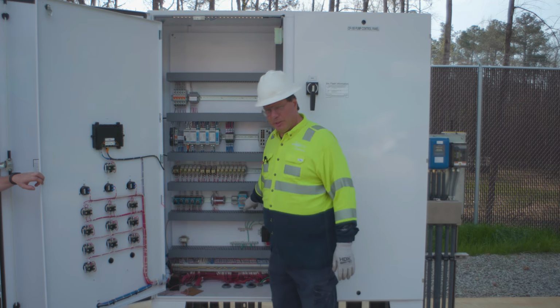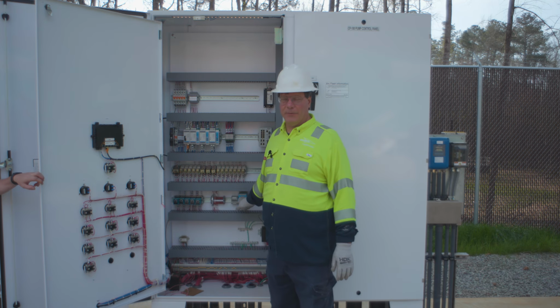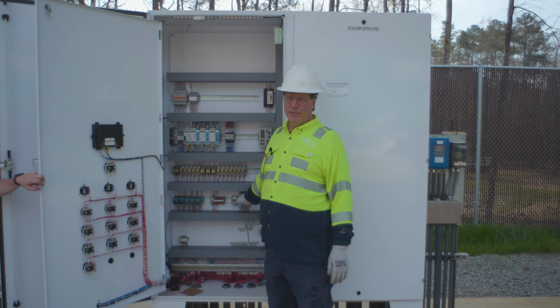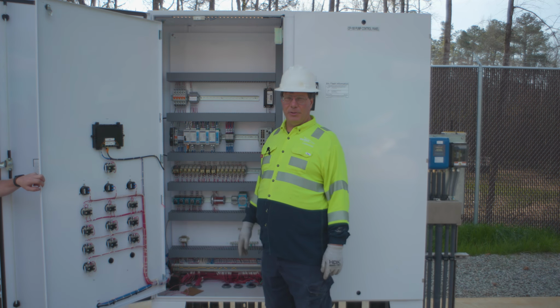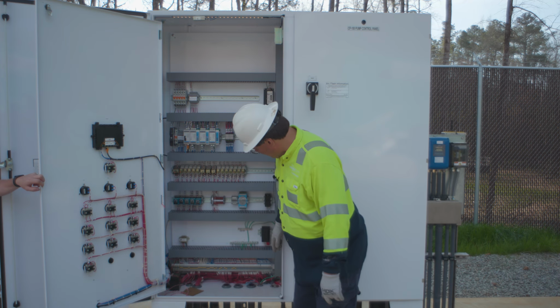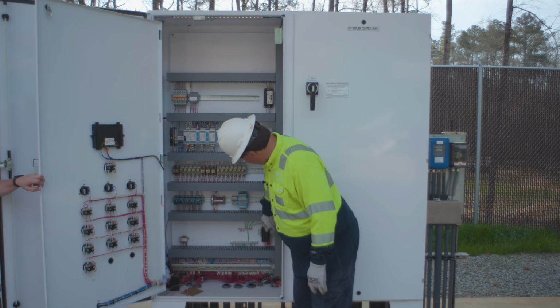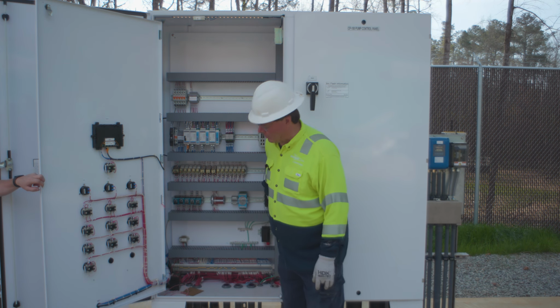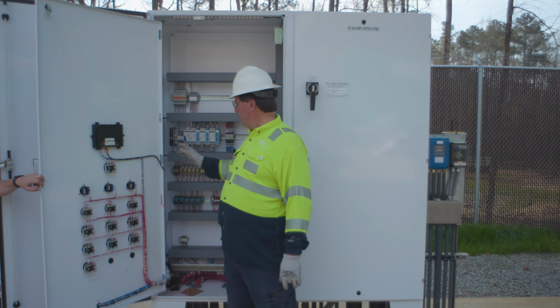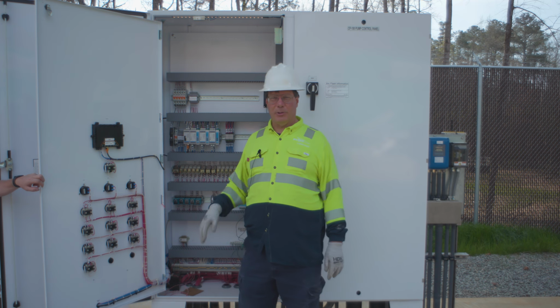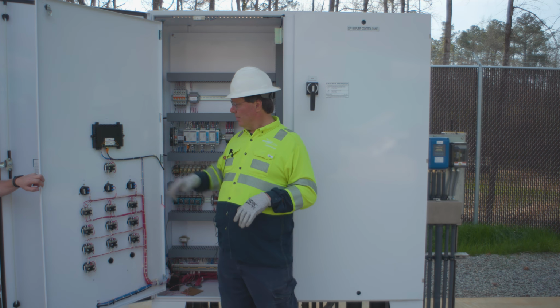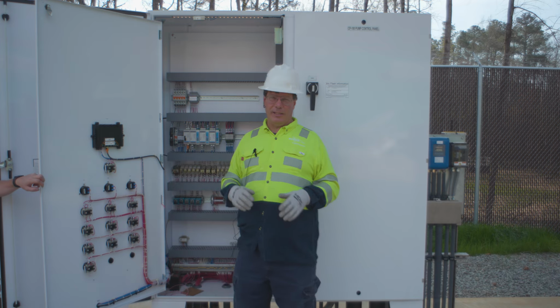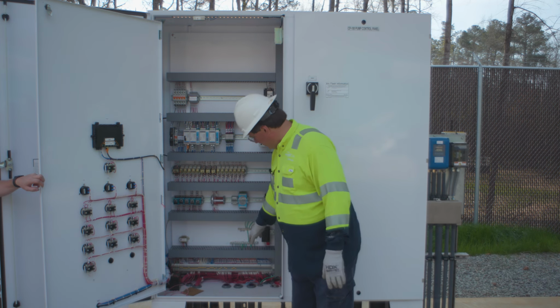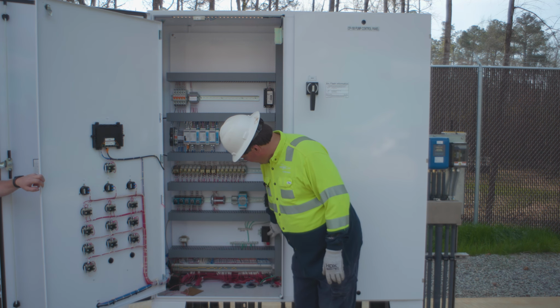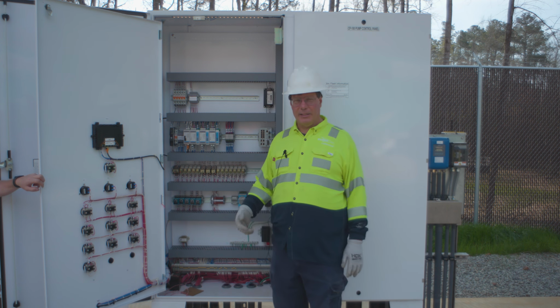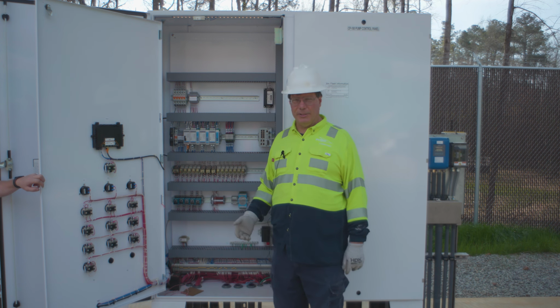This is for the mission unit. It's not used, but it's additional I/O if they wanted to add other things to the mission unit. And then down at the bottom is where you could plug in a laptop if you wanted to connect to the motor protection system and do programming with the laptop. You can, but you can also program through here, so it's not necessary. And then this is a heater to make sure we don't get in a condensation condition below 40 degrees inside the panel.